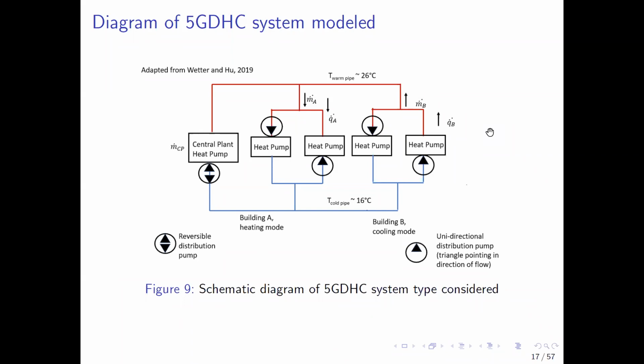The system configuration I considered is similar to that shown on the earlier diagram, with the warm pipe and cold pipe of the system operating at the temperatures shown, with bidirectional mass flow permitted through the network, and the energy transfer station with heat exchangers, circulation pumps, and water source heat pumps at each building, controlling mass flow to maintain a 10 degrees C delta T across the building.